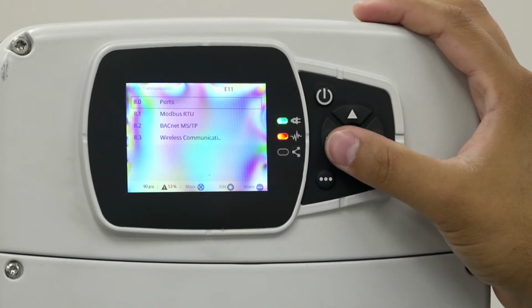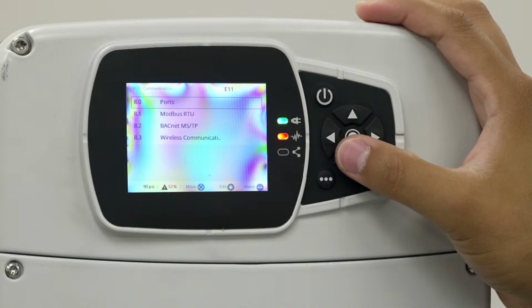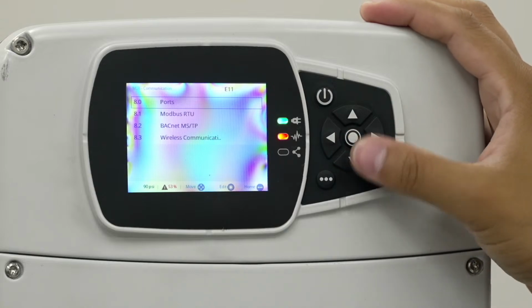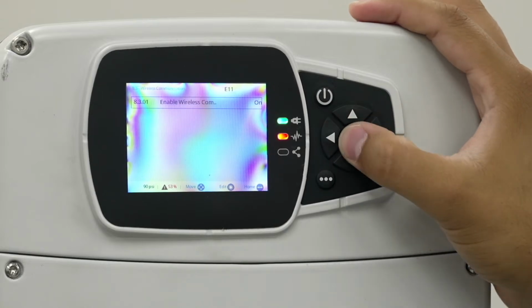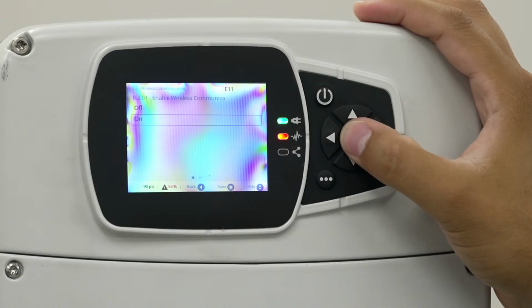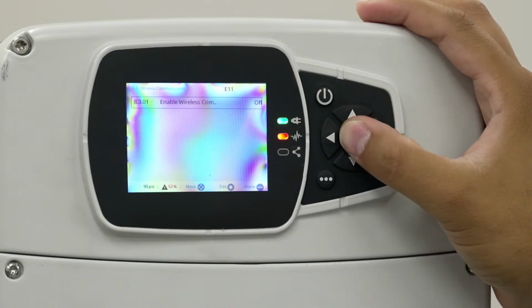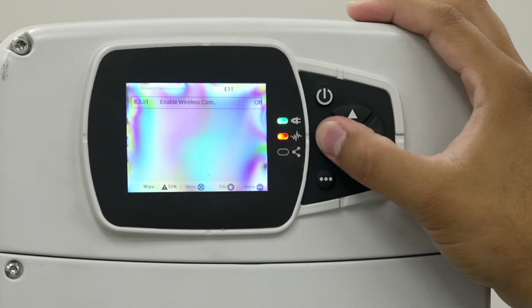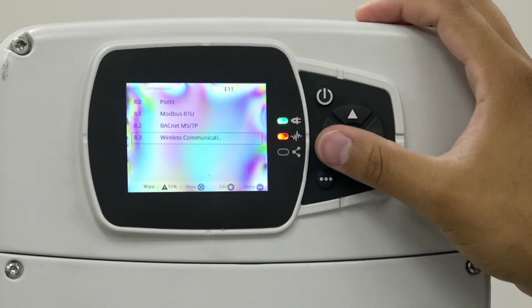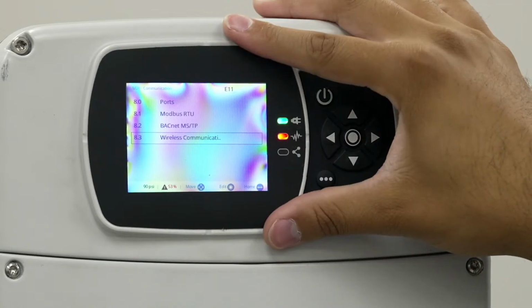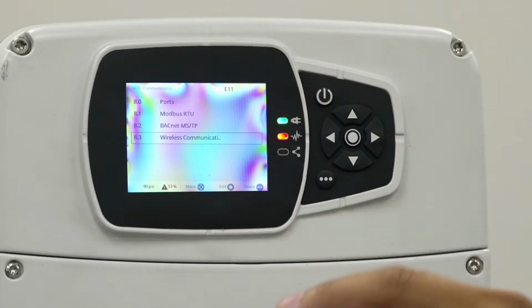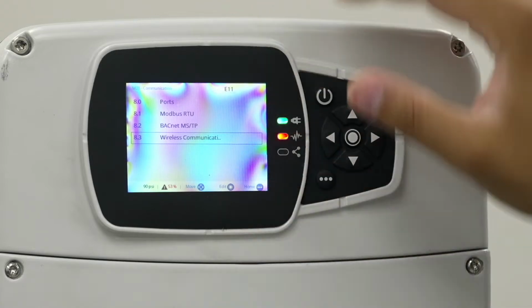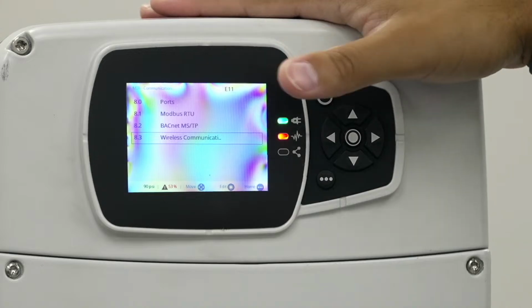Communication is where you would set these. A question I get quite a bit is about the Bluetooth connection. Can we turn them off? Here under wireless communication, enable wireless connection, I can switch this to off, so now Bluetooth will not be activated. And as we showed you earlier, the menu group is password protected, so someone still can't just come on and flip this back to on without knowing the password that's set on the VFD.